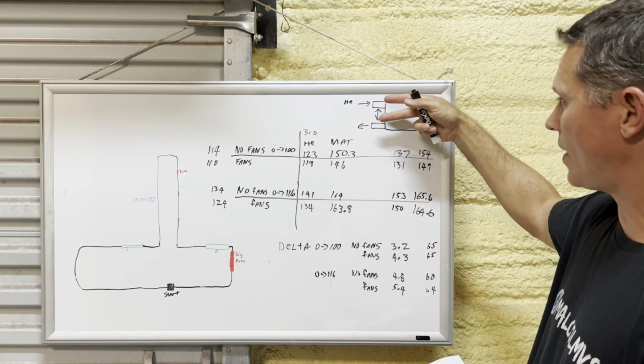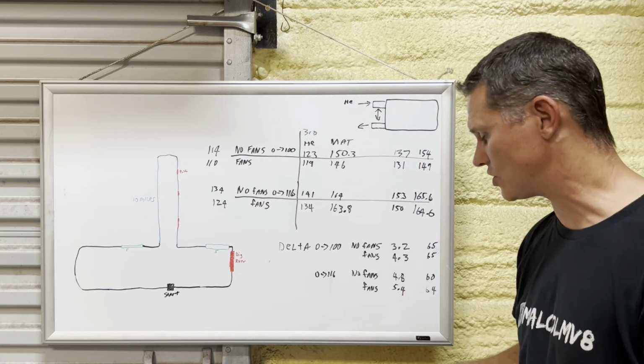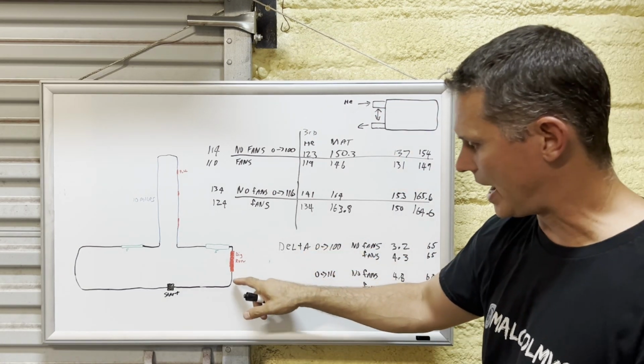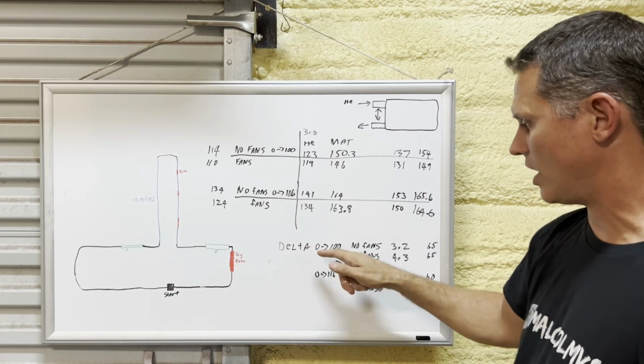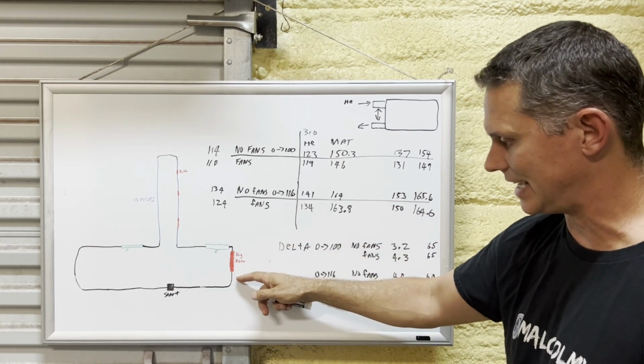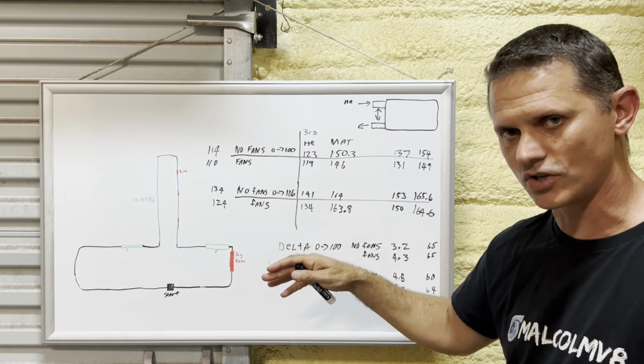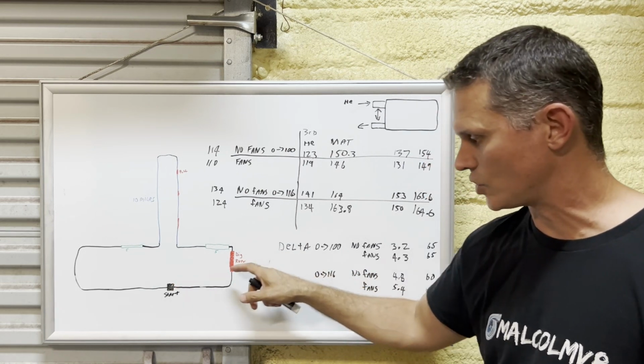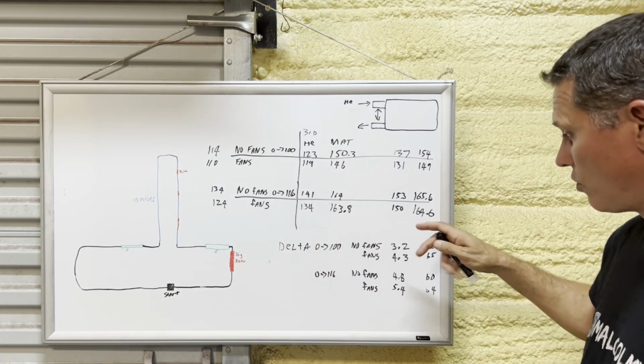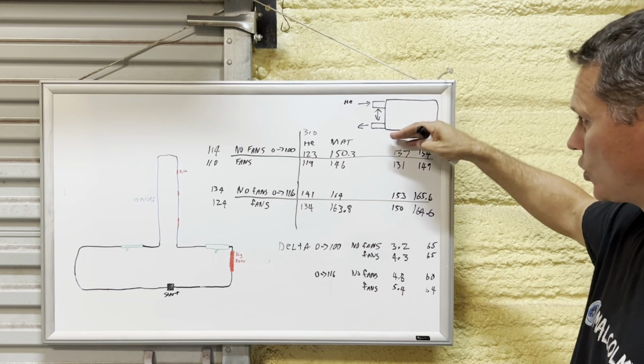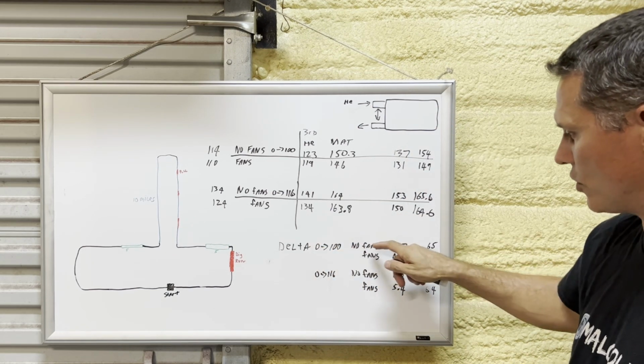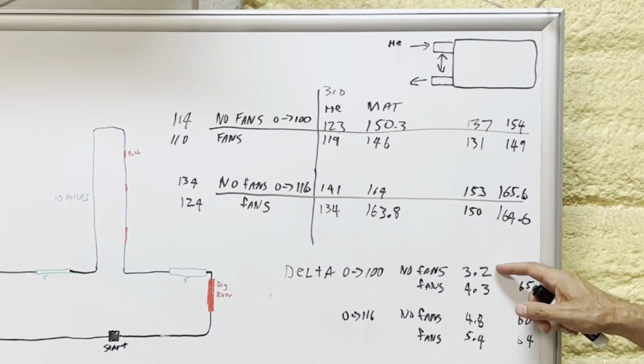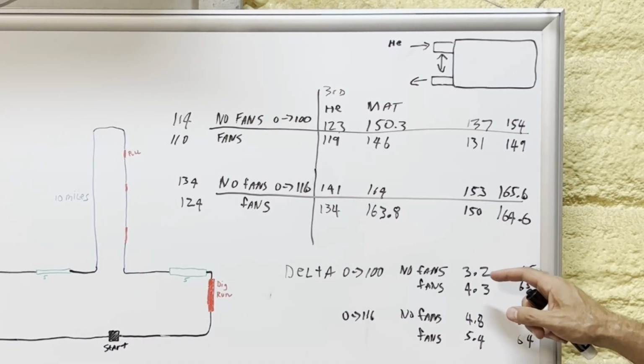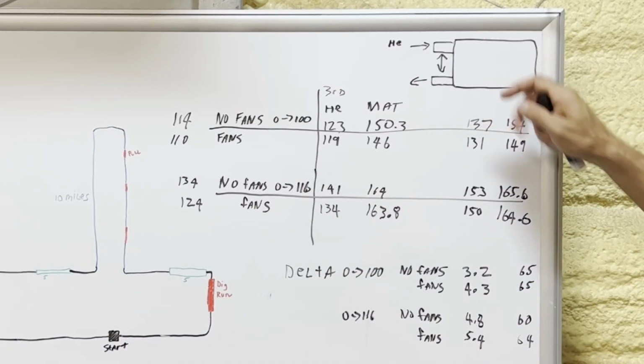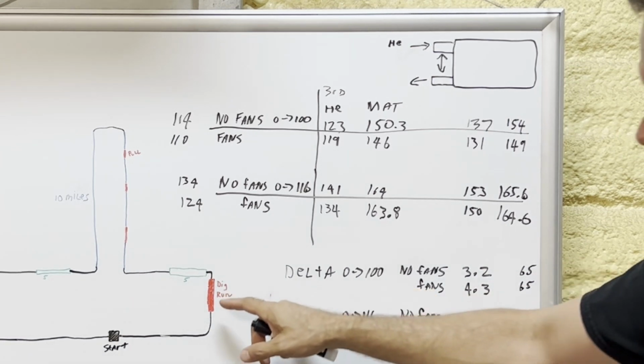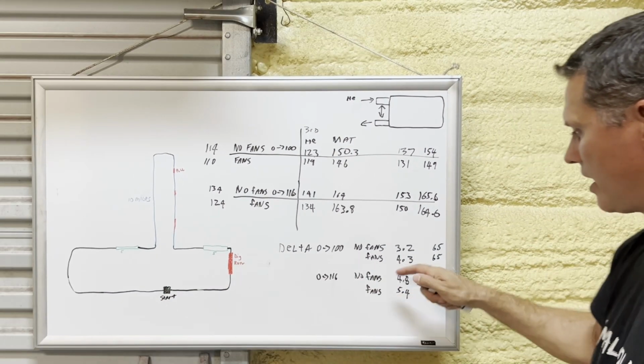And then, you're probably wondering, like, what's the delta across there? So this is on the cruise back after making these runs. After doing the 0 to 100 run and then letting out and letting the system kind of stabilize for just a few seconds and then cruising this whole way back, these are the deltas across the heat exchanger. In other words, how much it was cooling after 0 to 100 with no fans on there. We were getting an average of 3.2 degrees drop across the heat exchanger at 65 mile an hour, which was my average speed through all the lights and all the driving on the way back.